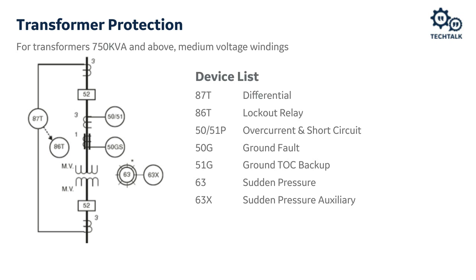On larger transformers, higher voltage applications, or if you have a particularly brave protection engineer, you might use additional relay functions. For example, on a generator step-up transformer, you'll most likely also use the 24 volts per hertz element. However, for the majority of medium voltage applications we see, this is the minimum recommended protection. For the most part, unless you have a specific need to use additional relay functions, just don't. As one of our most senior guys often preaches, my favorite element is the one that's turned off.